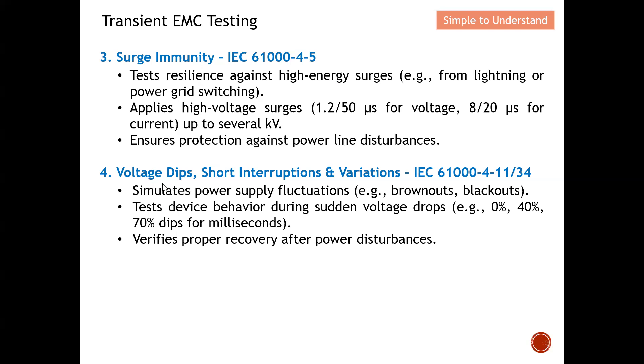Next is the voltage dip test. The key purpose is to simulate power supply malfunction — we dip the voltage in a very short time and see whether the DUT can still function. The test device behavior involves a sudden voltage drop, which can go all the way to zero, or 40 percent or 70 percent dip, in milliseconds. Some standards require the device to recover on its own, while some don't even allow a reset, so this tests whether the DUT can do a proper recovery after such a power disturbance.